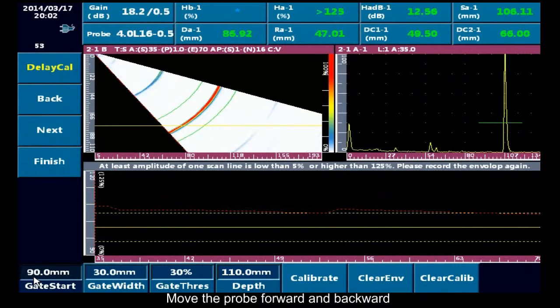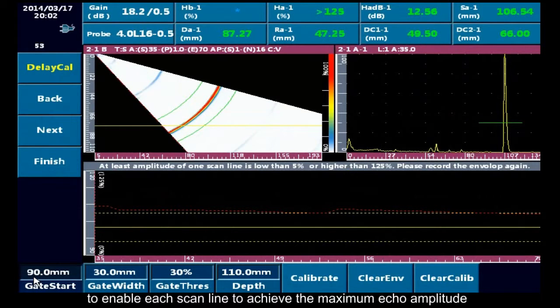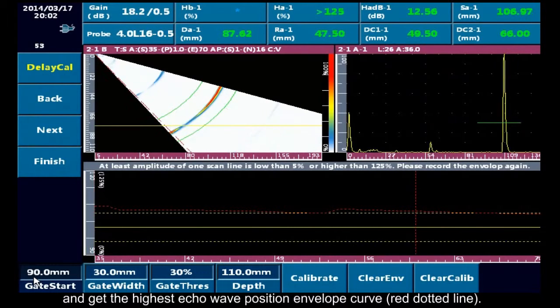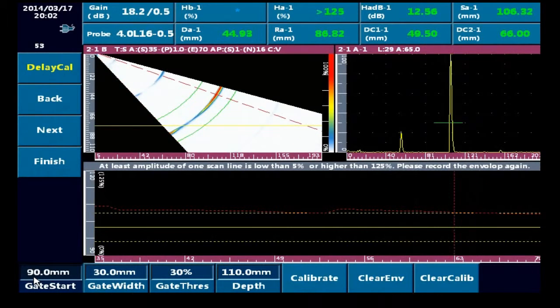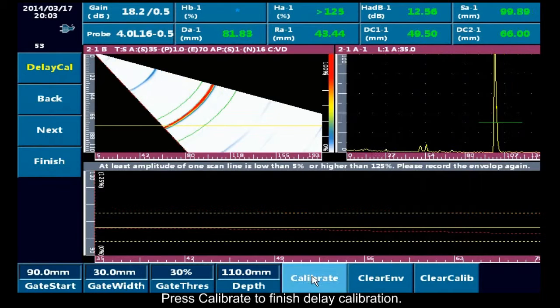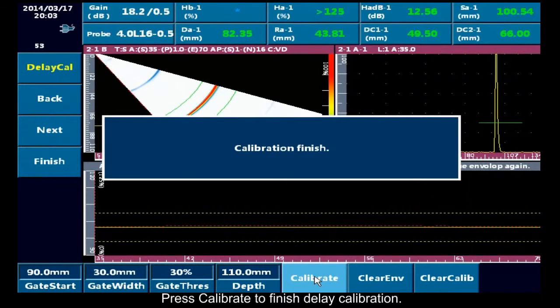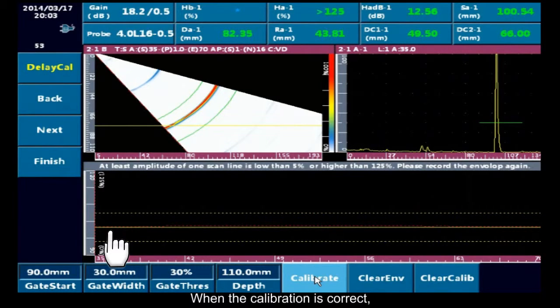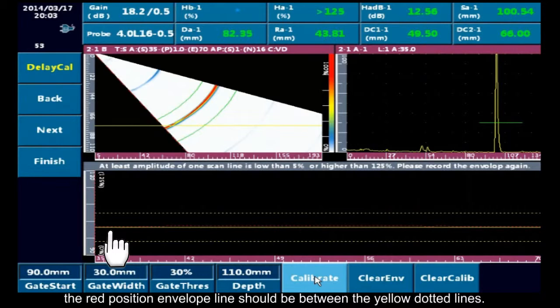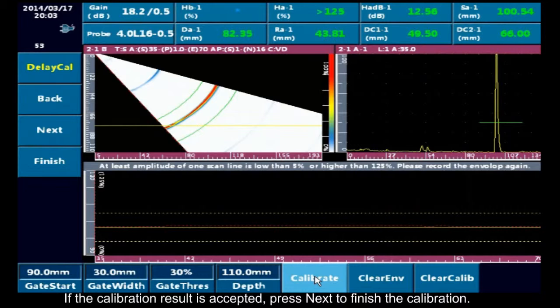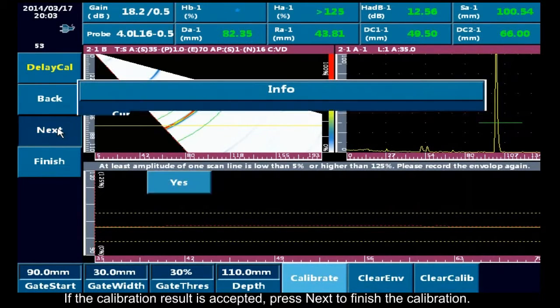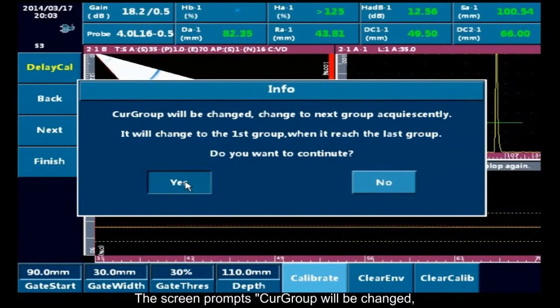Move the probe forward and backward to enable each scan line to achieve the maximum echo amplitude and get the highest echo wave position envelope curve. Press calibrate to finish delay calibration. When the calibration is correct, the red position envelope line should be between the yellow dotted lines. If the calibration result is accepted, press next to finish the calibration.